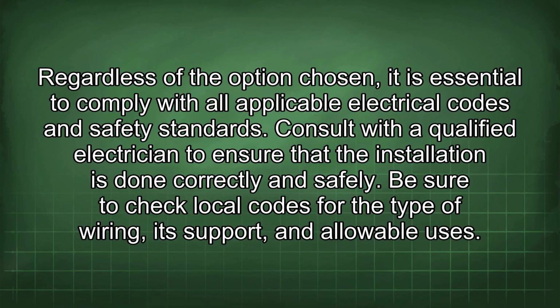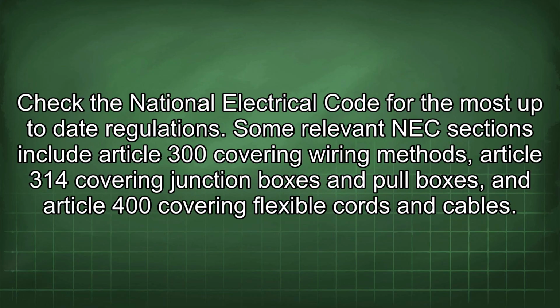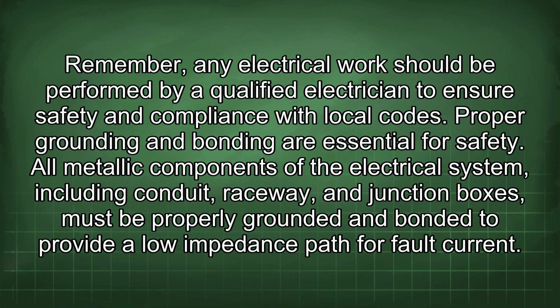Regardless of the option chosen, it is essential to comply with all applicable electrical codes and safety standards. Consult with a qualified electrician to ensure that the installation is done correctly and safely. Be sure to check local codes for the type of wiring, its support, and allowable uses. Check the National Electrical Code for the most up-to-date regulations. Some relevant NEC sections include Article 300 covering wiring methods, Article 314 covering junction boxes and pull boxes, and Article 400 covering flexible cords and cables. Remember, any electrical work should be performed by a qualified electrician to ensure safety and compliance with local codes.